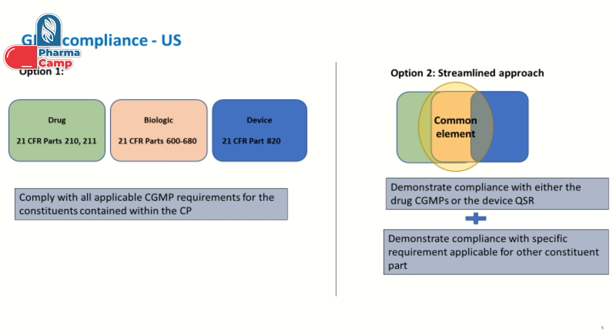This was a bit complex — why follow all the individual requirements for all components when some elements are common across these regulations? To address this, FDA introduced the streamlined approach in 2018. The streamlined approach is a new framework for GMP compliance for combination products, intended to simplify the GMP requirements and reduce the regulatory burden for manufacturers. Since these requirements have common elements, you can show compliance to those common elements and then fulfill the specific requirements of the other component, so you no longer need to show compliance with both drug and device GMP requirements separately.